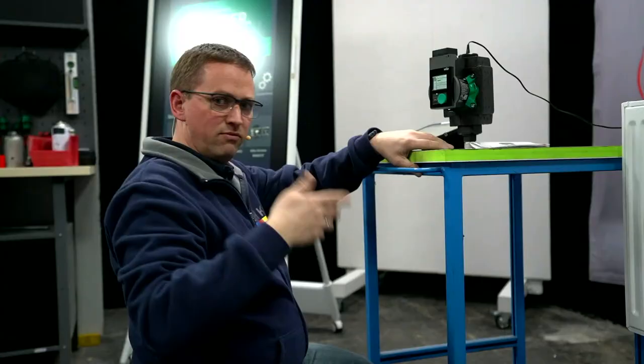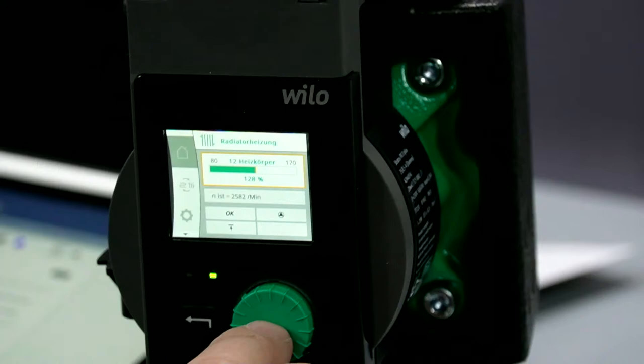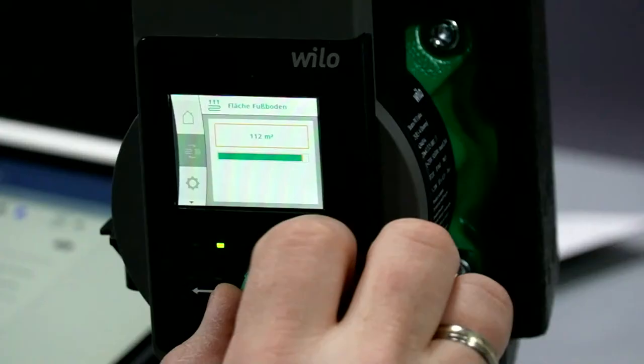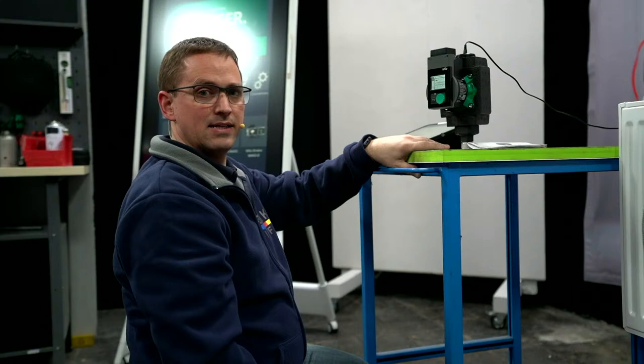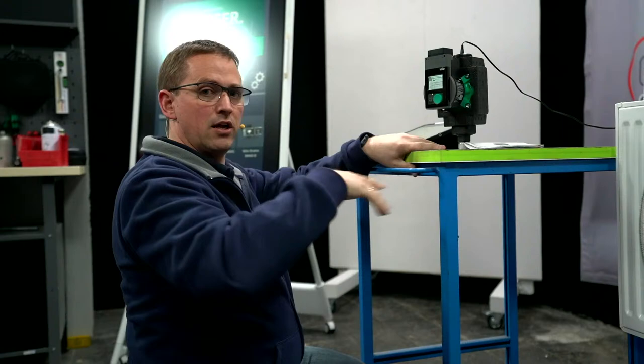Diese zwölf Heizkörper heißt ja nicht, dass sie auf jeden Fall alle gut versorgt sind. Es ist auch immer die Frage, wie viele und wie groß die Heizkörper sind, wie weit die verstreut sind im Gebäude. Dann kann ich hier prozentual in Einprozent-Schritten einfach die Leistung anpassen. Das Gleiche gibt es auch im Einstellungsassistenten für die Fußbodenheizung. Hier kann ich einfach die Quadratmeter der Fußbodenheizung eingeben – wie geil ist das denn? Ich trage einfach ein, ich habe 110 Quadratmeter. Kann auch da prozentual anpassen, wenn es von der Leistung nicht passt. Die Pumpe wählt automatisch den richtigen Modus, um den Heizkreis zu versorgen. Die Pumpe mit 4 Meter kann bis zu 120 Quadratmeter Fußbodenheizung versorgen.